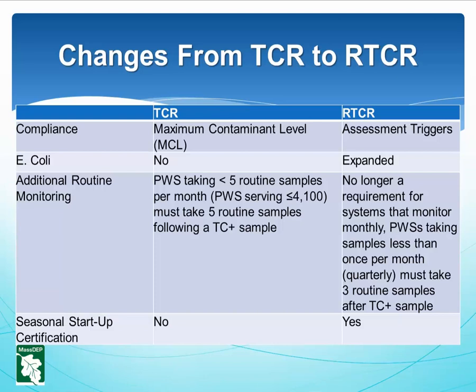Key Changes from TCR to RTCR. The Total Coliform Rule (TCR) established a maximum contaminant level (MCL) based on the presence or absence of total coliforms, and also requires sanitary surveys for systems collecting fewer than five samples per month. The Revised Total Coliform Rule (RTCR) established an MCL for E. coli and uses E. coli and total coliforms to initiate a find-and-fix approach to address fecal contamination that could enter the distribution system.